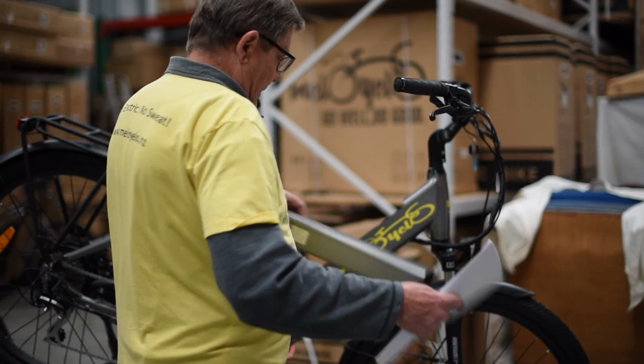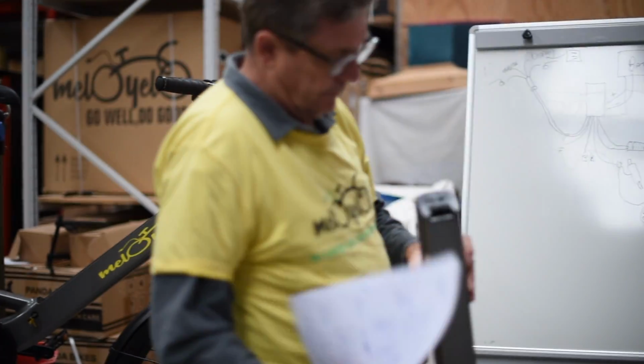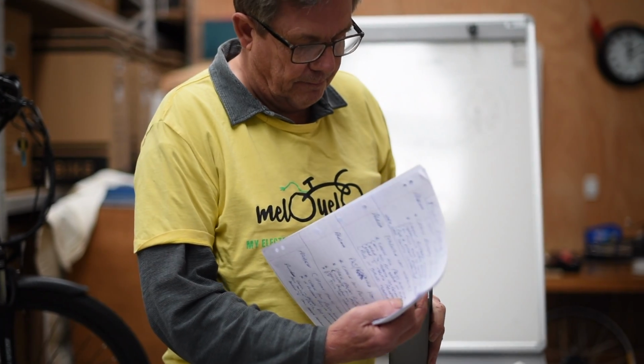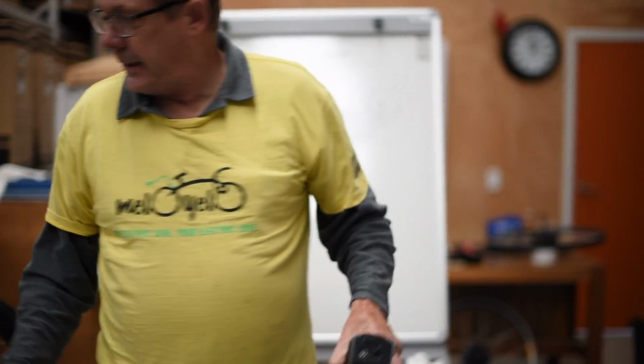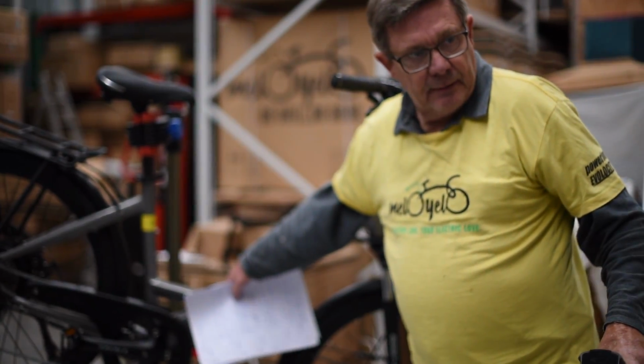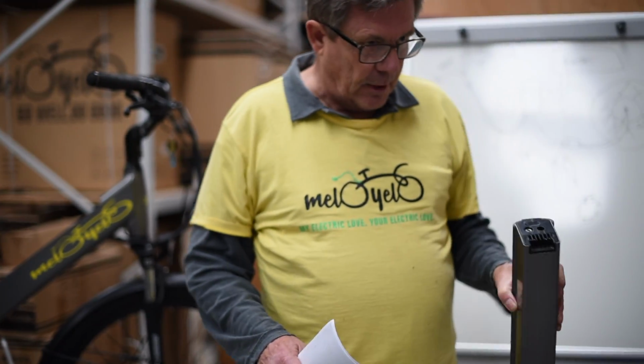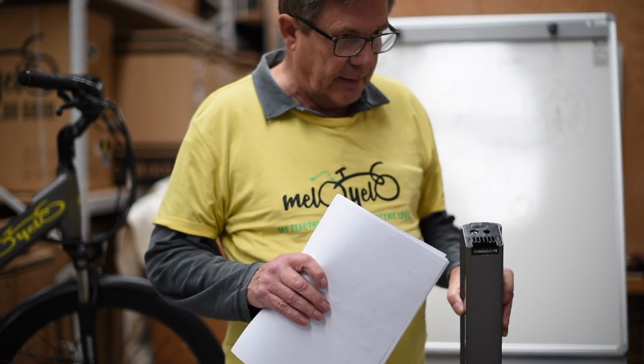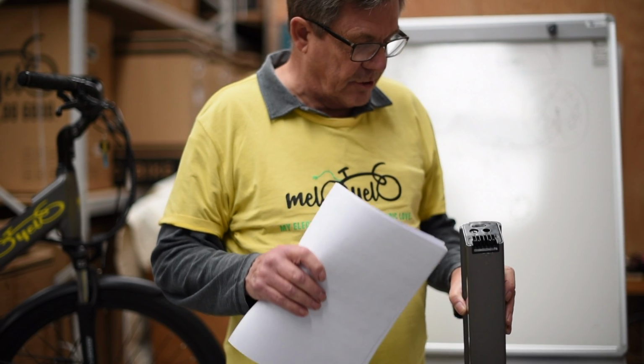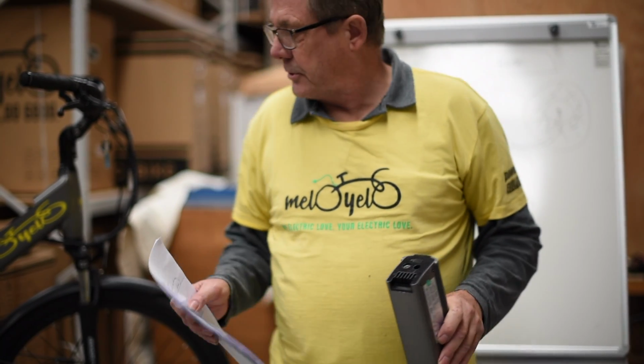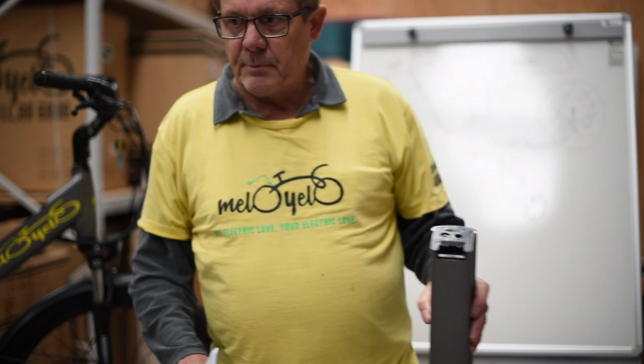If the battery's not turning on, the first thing I would check is basic battery connections. They all have little pins in there that connect onto the connectors. Over time, with vibration and things going on, those pins can get weaker, and you need to go in there and check that they are making good contact. So that's the first place.